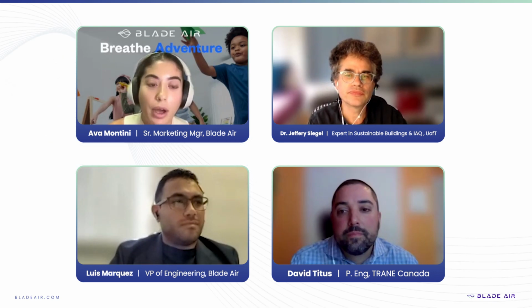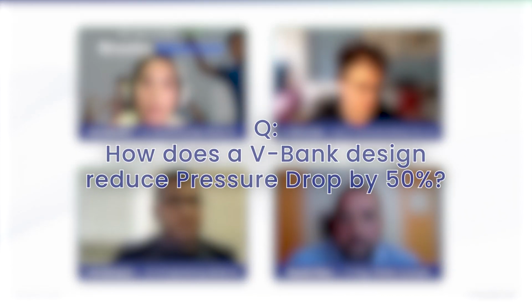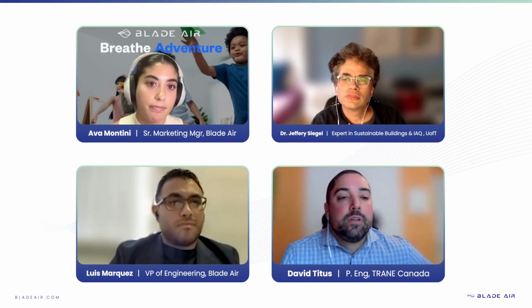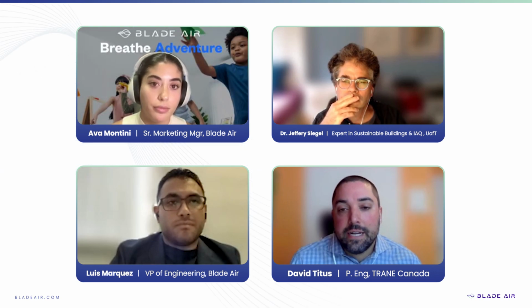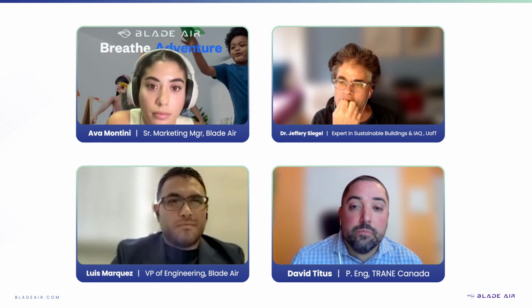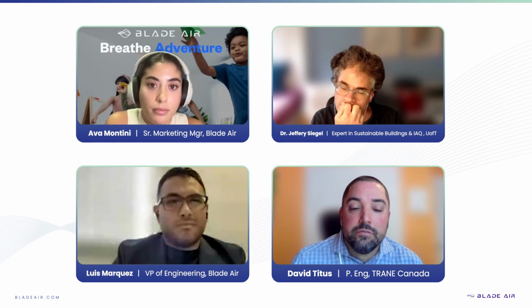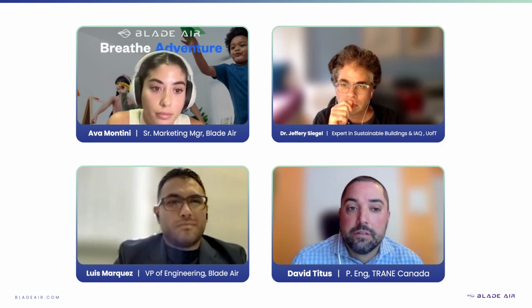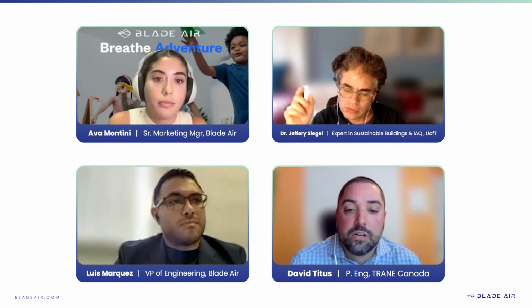Can you please explain how a V-bank design, which utilizes the polarized media filters you were just previously referring to, how this V-bank design will reduce the DP by 50%? Yeah, thanks for the question. So the reduction is in comparison to a flat filter existing. What I've seen in a lot of units is when you have an existing unit that has two filters side by side, there's enough space in that filter cavity to actually physically remove the two filter racks and install a V-bank filter rack, a simple 2-inch V-bank filter rack, which isn't a big construction achievement by any means. It's not a huge cost.